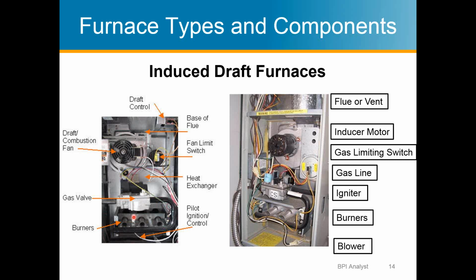On these systems, it's very hard to check for spillage. I've seen and heard a lot of people talk about different ways to do it, like around these seams. It's not a very good check. Some people will check for spillage around here. That's another option. I've never seen one spill from either one of those places, but you can do it.